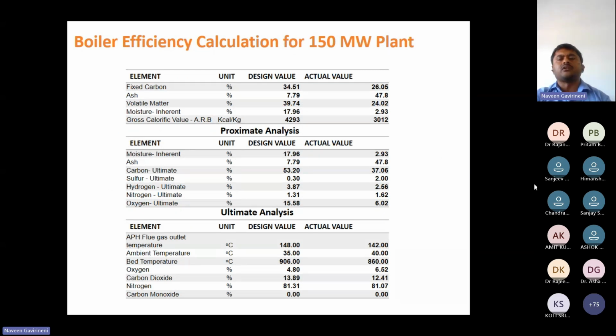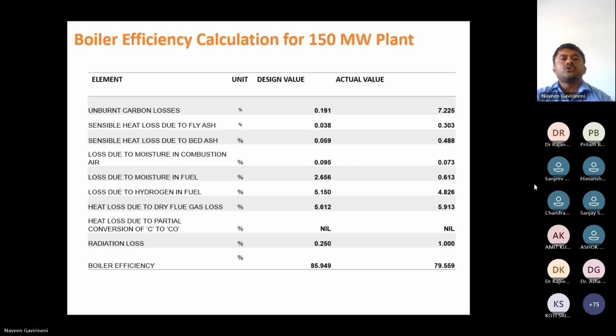This is my company's calculation. This is the design fuel, with proximate analysis and ultimate analysis. These are the parameters needed for calculating the boiler efficiency. So these are the design losses. The design efficiency is our design efficiency from the OEM. They have given 86%, but it will come to only 79 to 80%.